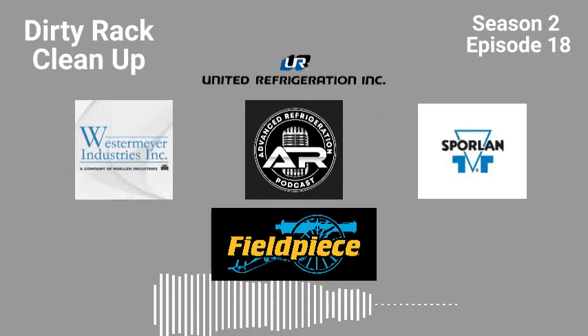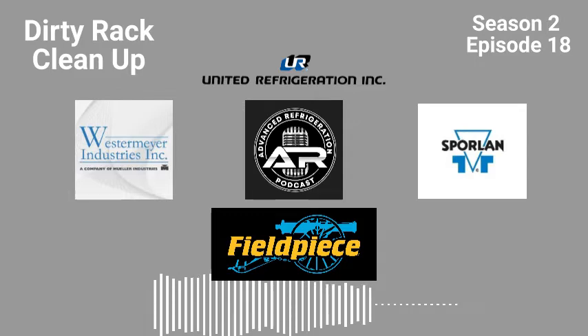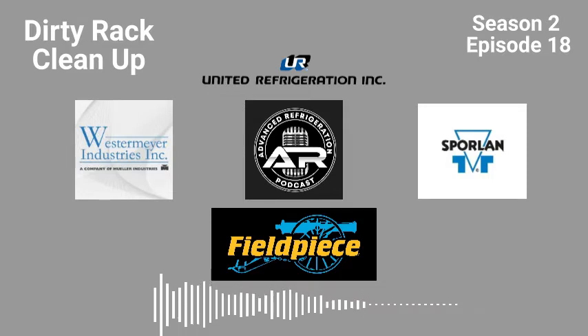And speaking of seeing stuff on the internet, I've seen a bunch of pictures people have been posting of the inside of compressors. In the past month, I've probably seen about 20 or 30 pictures where you see really, really bad copper plating. Don Gillis showed a crank on a small K body where every single journal was just coppered up. People are taking pictures of some of the heads where you get that dark red tinge. Just a boatload of moisture in some of these systems.